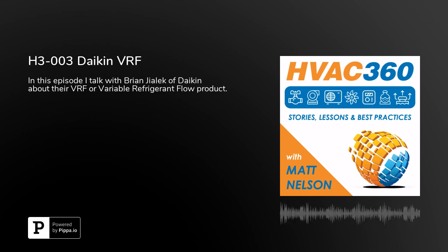Now, is there a difference between the regular heat pump and the heat recovery? Sure. Good question as well. The heat pump is typically a 2-pipe system. You have a liquid and a suction side. For the heat recovery side, you'll have 3 pipes: a liquid, suction, and a gas. So that third gas line is important for bringing some additional refrigerant from the outdoor unit to supply heat to other areas of the building, as well as take heat from one area of the building and move it to another area. So it's basically a transit of hot gas that's going through that system.